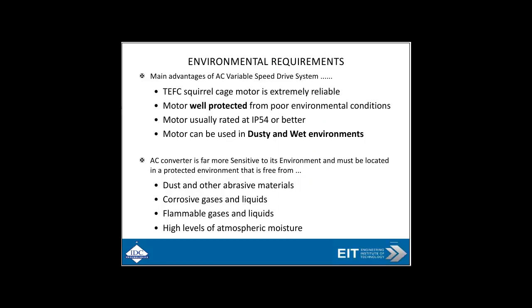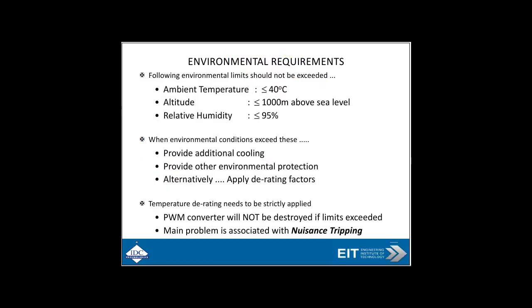Environmental requirements: the squirrel cage motor is pretty reliable and is protected for poor environmental conditions, so you can use it in dusty and wet environments. But the actual converter itself is very sensitive to dust, corrosive gases, liquids, and high atmospheric moisture, so you've got to be more wary about the converter than the motor itself. Environmental requirements include ambient temperature less than or equal to 40 degrees, altitude less than 1,000 meters, and relative humidity less than 95 percent. These are all very important issues in the design of variable speed drives.